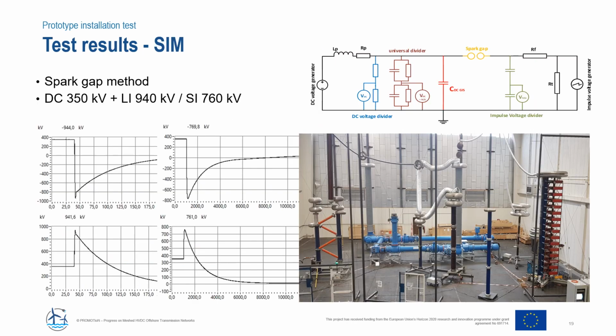Some test results. Before the test results, you see the photo of the HVDC GIS under test. On the right side of this photo, you see a DC source connected to the bushing of the GIS. So 420 kV is supplied from there. And there is an impulse generator on the right side, which can generate lightning as well as switching impulse. This has been superimposed through a spark gap. There are different methods. We use the spark gap method. For example, a capacitor coupling method could be used.